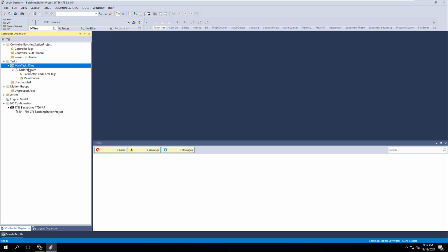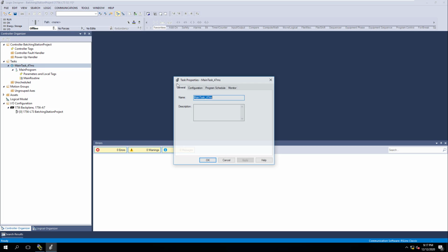If you think about a rollover, when you come in here and you're online, you can click monitor and you'll see your scan times, your max and last, and then it will also have your intervals between scans. So if there are any problems with your scanning, you'll have task overruns or overlaps, right? An overlap means there's a problem. That means your processor's not going to respond properly.